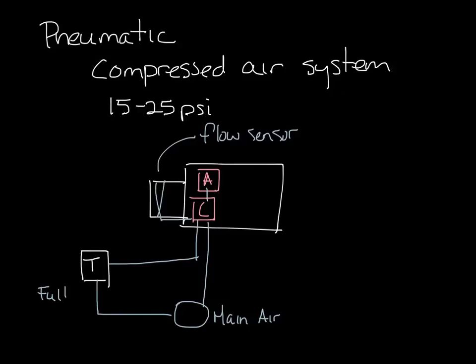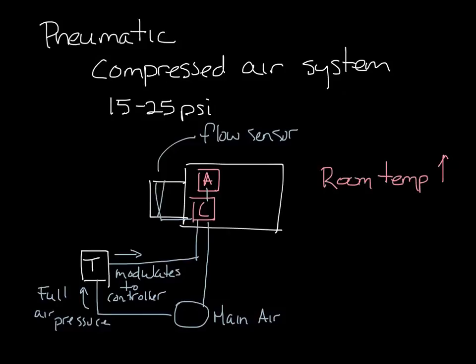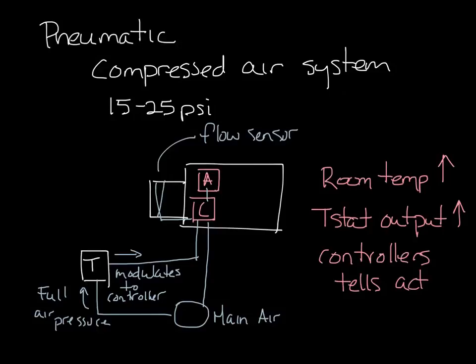The thermostat receives full air pressure from the main supply air. And it modulates the output pressure that goes to the controller to tell the controller whether it needs to open or close the damper. So when the room sensor senses an increase in temperature, the thermostat output pressure increases as well to the controller, which tells the controller to open the damper and supply more air to the space.